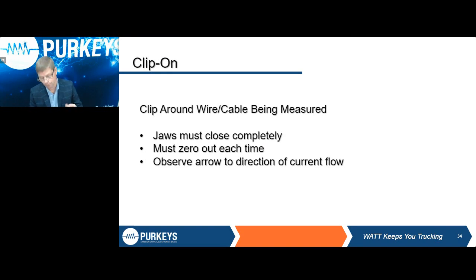But a clip-on is very accurate if you buy the right type. When I say the right type, it's just like anything else, you get what you pay for. Depending upon what you're trying to test, the size of the jaws can make a huge impact. I've got one that will read up to 2,000 amps. It has a very large jaw. The problem with that is it's not going to be nearly as accurate on small loads. Also consider the quality of them, and how well they are shielded. So those are things you've got to be aware of when you look at them.